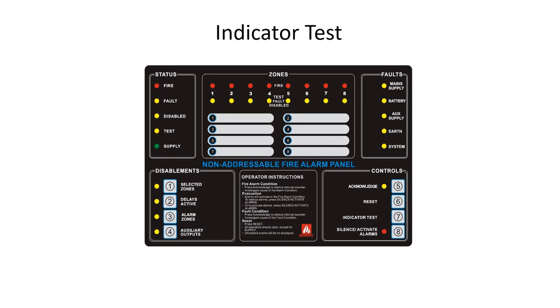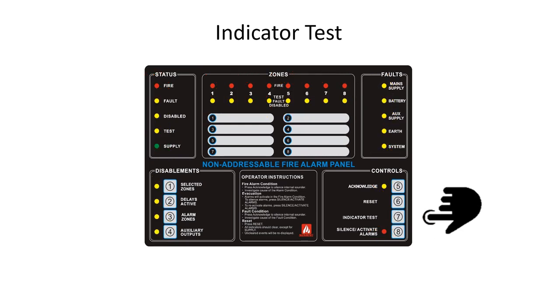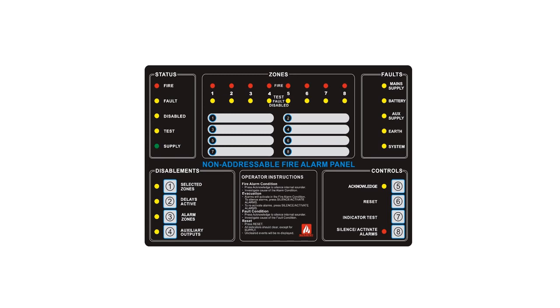Next, we can undertake the indicator tests. Simply press the indicator test button. The internal sounder will operate and all the LED indicators will be on until the indicator test button is released. The panel can be easily configured to optimize detection and alarm performance for each building.